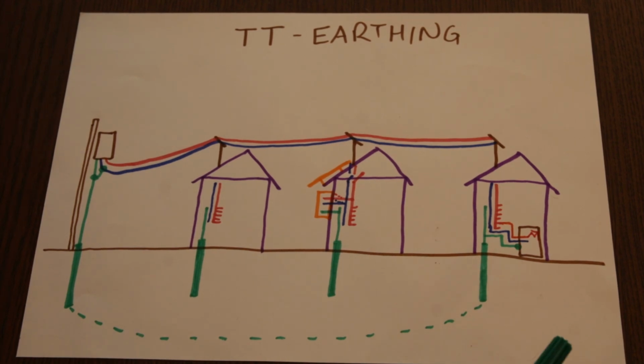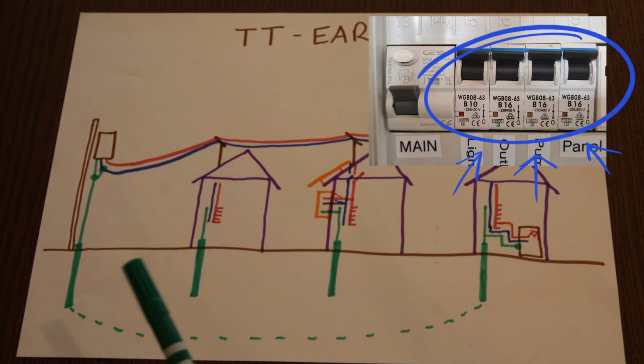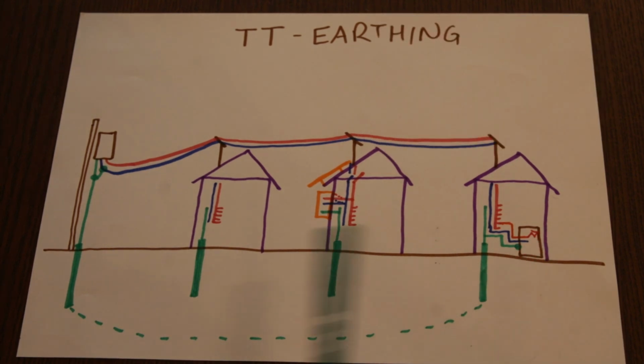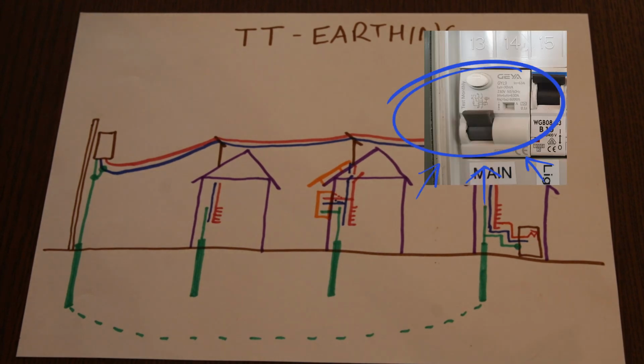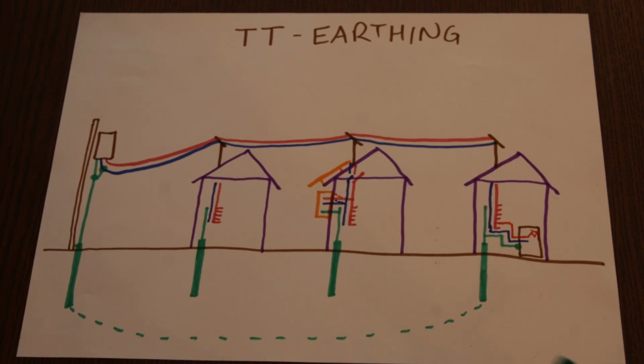We are always talking about impedances. The impedance for this return current, which now has to go through 2 grounding rods, which of course have quite high resistance compared to, let's say, a return path wire. These return currents are usually not capable of tripping our normal line breakers, like the MCBs which you have in your distribution panel. They will require a special form of protection, and this is done by so-called RCDs. They would of course trip much sooner. Instead of tens of amps, they only require milliamps of fault current to trip the protective device.